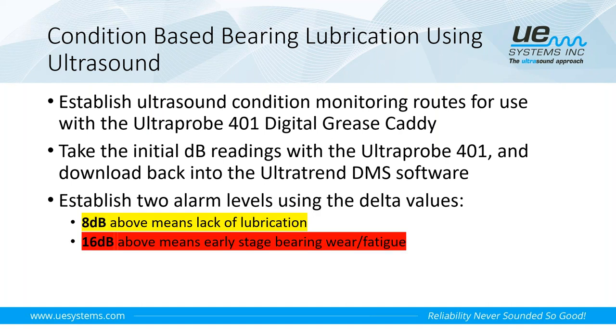So once we've established our baseline, then we can set those 2 alarm levels that I referenced earlier. And these are the recommended values when it comes to establishing your 2 alarm levels. And you can set those based off of these delta values. So if you have an 8 dB increase above your baseline, that means a lack of lubrication for that bearing.